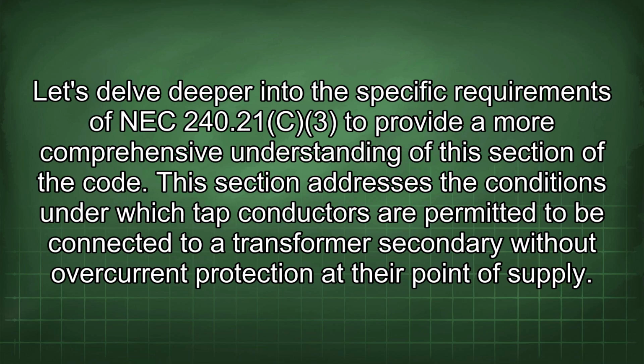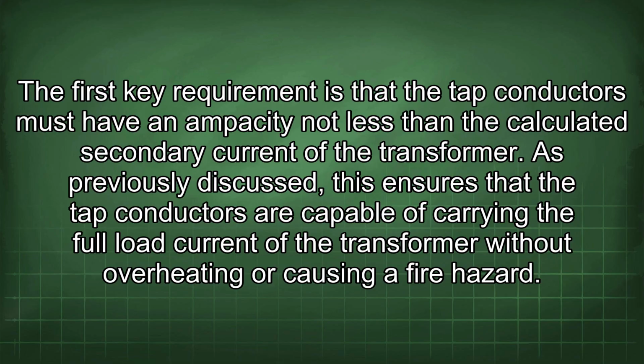This section addresses the conditions under which tap conductors are permitted to be connected to a transformer secondary without overcurrent protection at their point of supply. The first key requirement is that the tap conductors must have an ampacity not less than the calculated secondary current of the transformer. As previously discussed, this ensures that the tap conductors are capable of carrying the full load current of the transformer without overheating or causing a fire hazard.